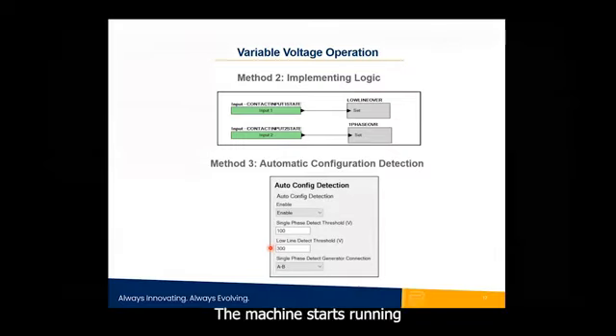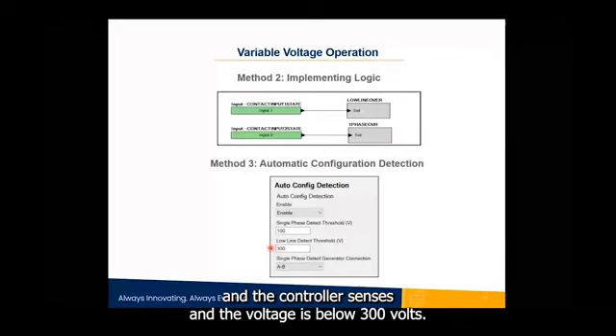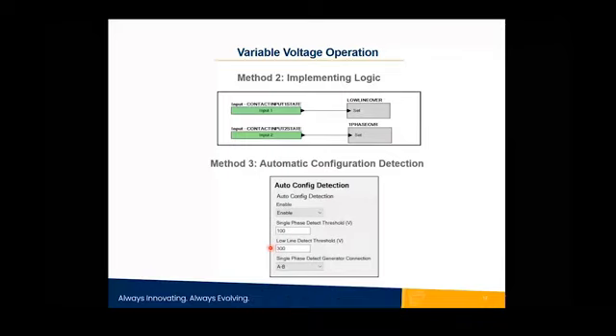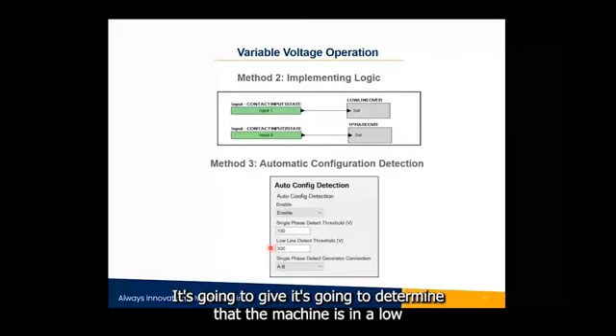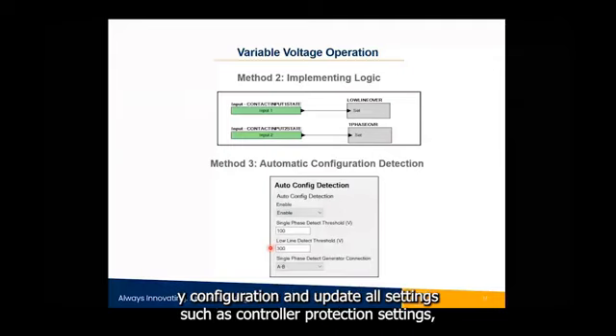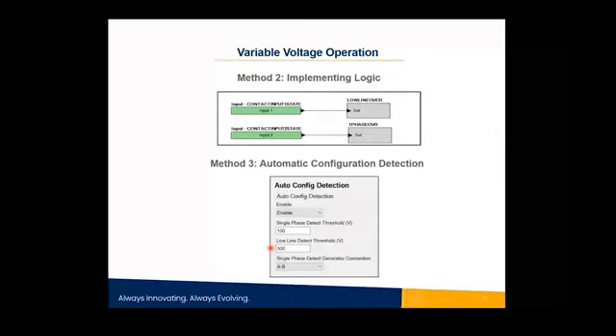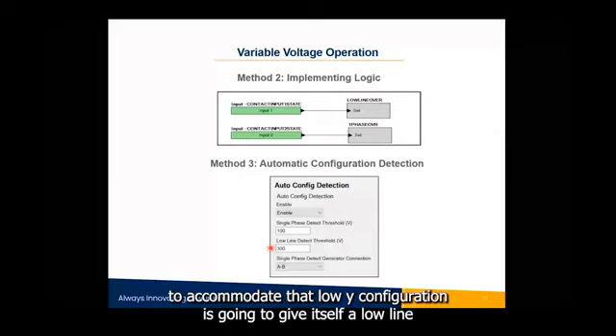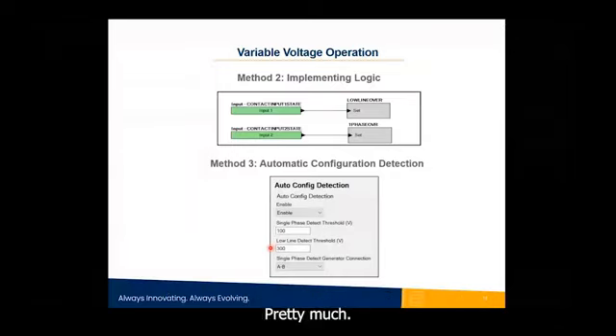The machine starts running and the controller senses that the voltage is below 300 volts. It's going to determine that the machine is in a low Y configuration and update all settings, such as control and protection settings, to accommodate that low Y configuration. It's going to give itself a low line override status, pretty much.